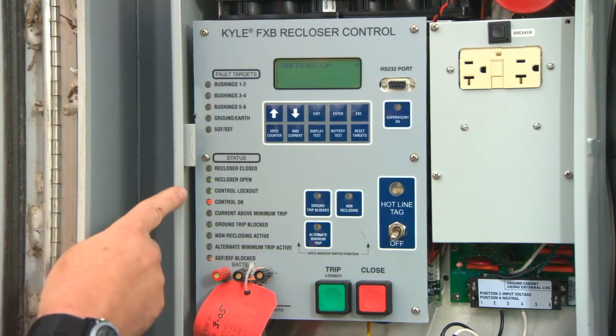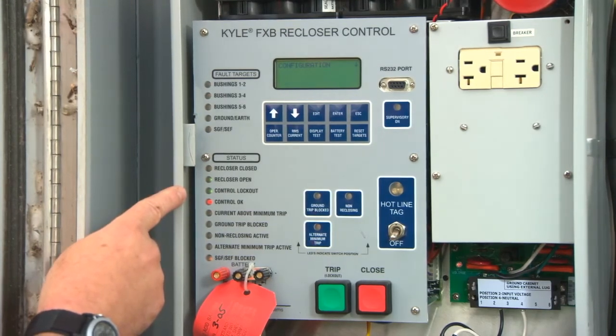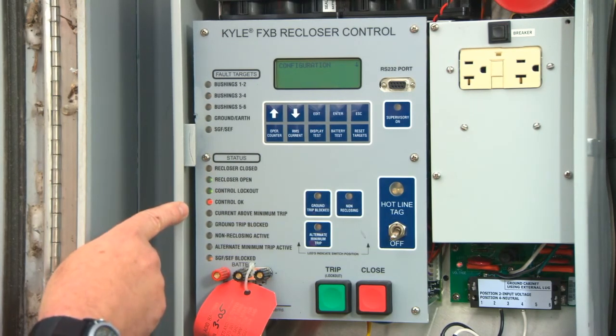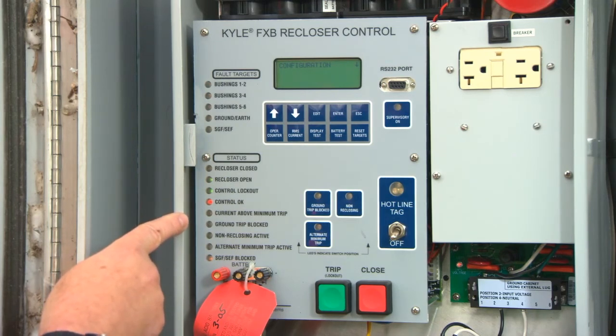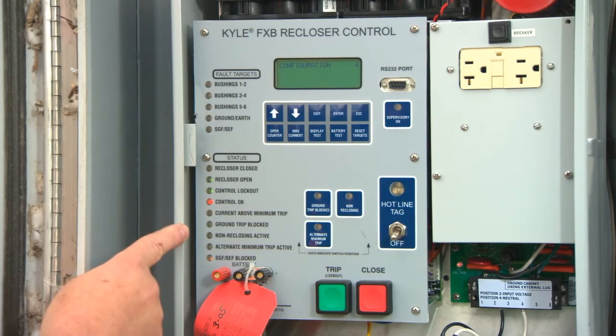A green LED also indicates a control lockout. If the control has gone to a lockout state and all contacts are open, this light will be on. Control OK. This unit performs self-diagnostics. If the control is functioning properly, this LED will be red at all times. Current above minimum trip will only be illuminated during the time that the unit is in a trip condition. Ground trip blocked. If one were to set the ground and block it to prevent it from activating on ground, this LED would be illuminated.